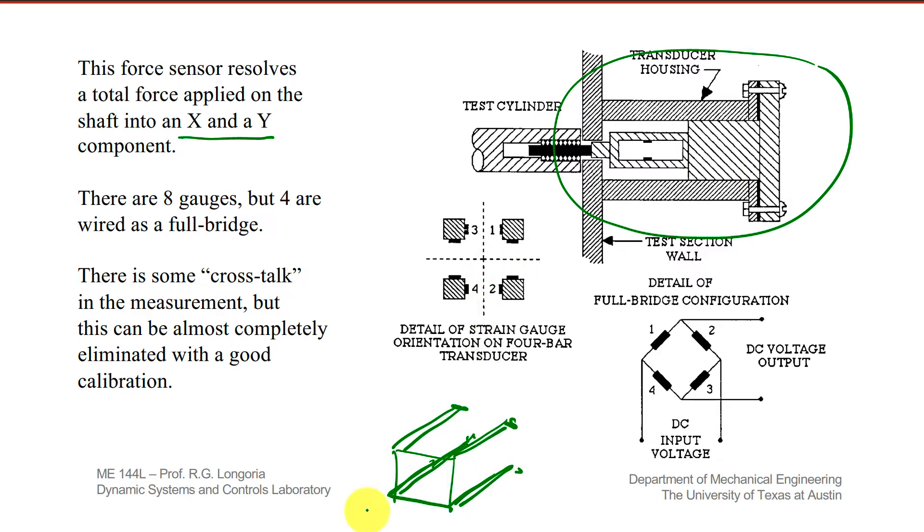Looking at it from this face, you basically have two bridges. One is on the interface of these beams, and the other is on these interfaces. So any forces in this direction, you can figure that like a full bridge. Forces in this direction, you use these four gauges to measure, say, the X, and here to measure the Y. Each one of those is wired separately as a full bridge. And so you can measure XY forces.